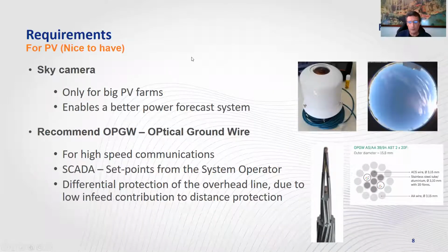Okay. For instance, for PV in Portugal, we have put a requirement, and this is also useful in the United States, to add sky cameras that allow us to detect the clouds that diminish the solar radiation, and this enables us to have a better power forecast of the system. Another requirement that we have is the OPGW, the optical ground wire, that enables fast communications and connectivity between the system operator and the plant.